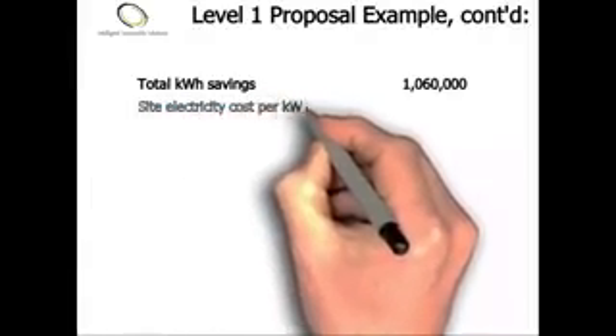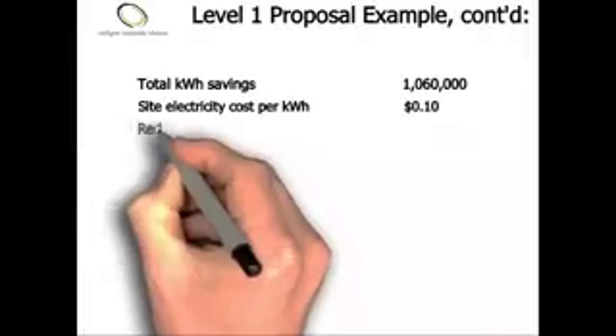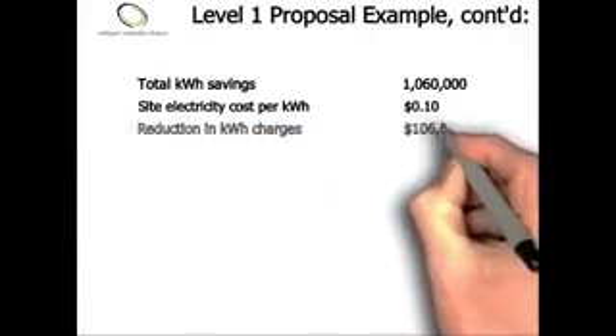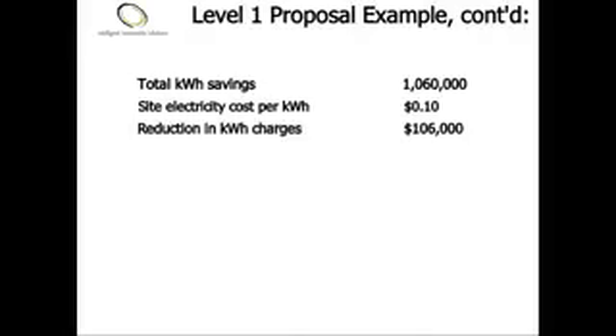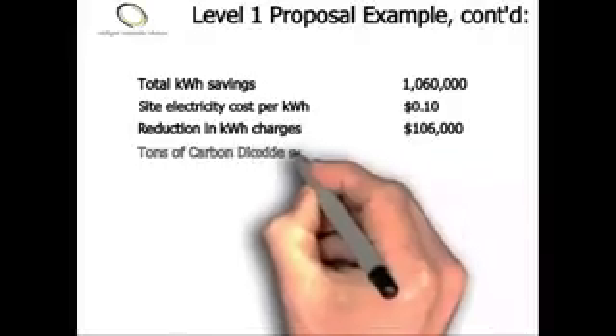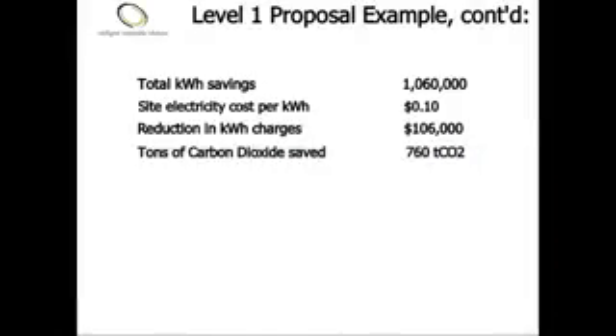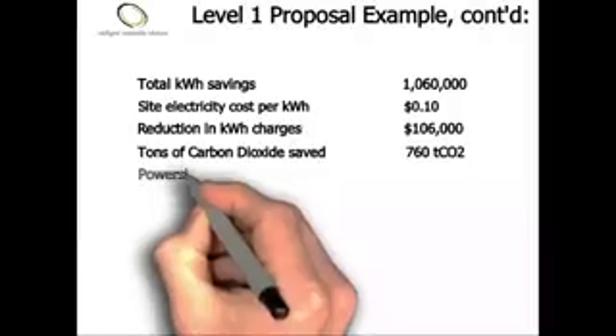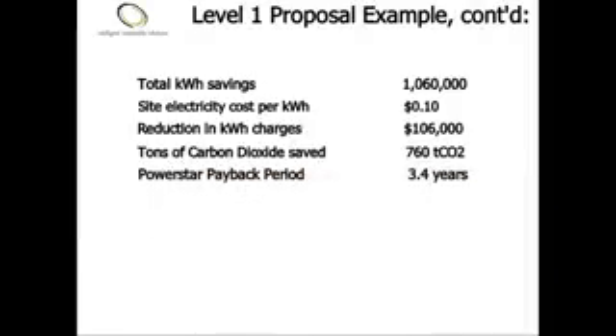If we use the approximate USA average of 10 cents per kilowatt-hour, that can vary, of course, depending on what part of the country you're in. Payback time is improved dramatically in places like Puerto Rico, where electricity costs can be as high as 25 cents per kilowatt-hour. So, using 10 cents times 1,060,000, this equates to $106,000. There are additional benefits, including carbon dioxide reduction, which will contribute to your company internal CO2 targets. In this case, using industry standard calculations, we save 760 tons.